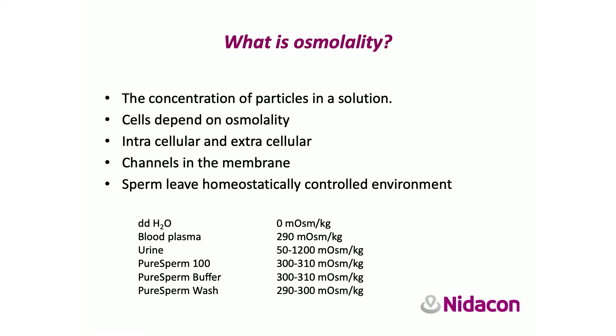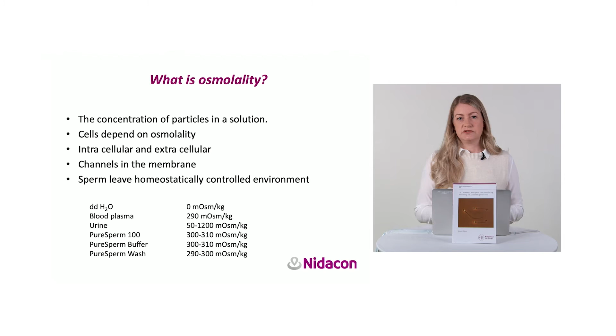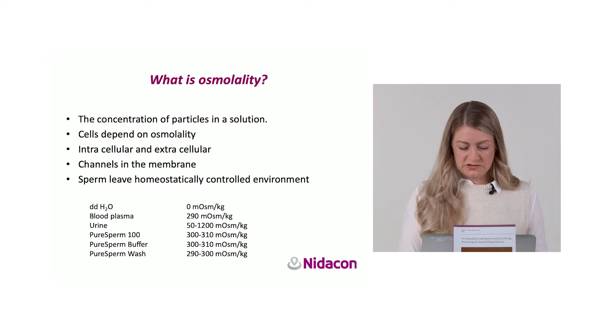All of our PureSperm gradients have an osmolarity of between 300 to 310 milliosmol. PureSperm buffer also has an osmolarity between 300 and 310 milliosmol. PureSperm wash, on the other hand, has a lower osmolarity between 290 to 300, and this is because of the gradual decrease in osmolarity that the cells will encounter when going into the culture medium. This osmolarity has been adjusted specifically since it comes in contact with the sperm. The sperm sample most likely starts at 290 at ejaculation.